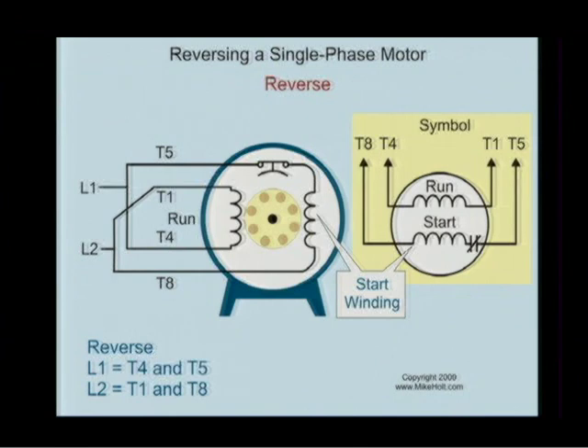We might just want to make the point that if you did have a dual voltage motor, hold on. I'm glad you brought up voltages. Would this matter? Can you only reverse a single-phase motor if it's phase-to-phase? Can you do this to a 120-volt motor? It doesn't matter. Yes, a washing machine motor. The difference being if it's a dual voltage motor, then you've got two run windings in there that you're going to hook up either in series or parallel.